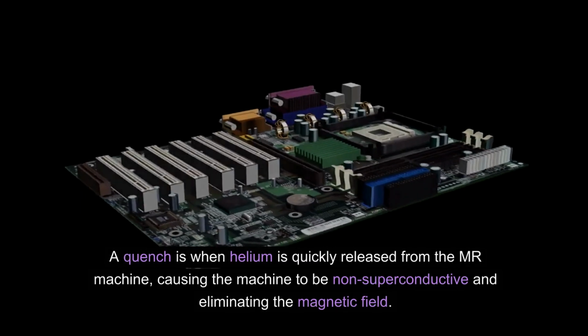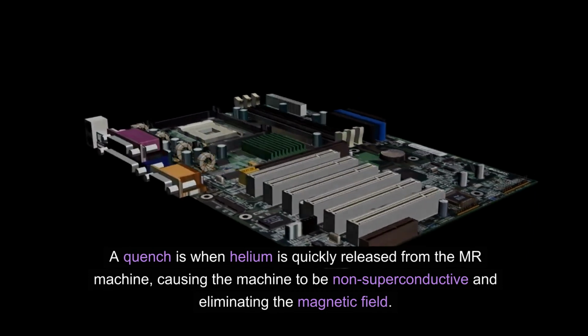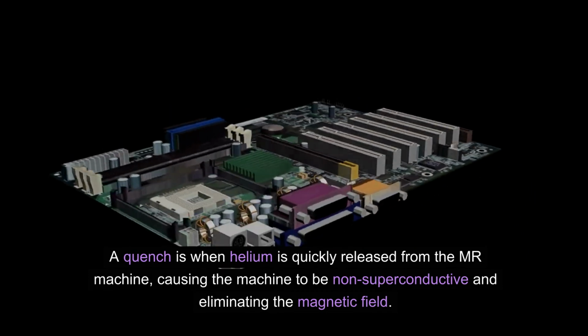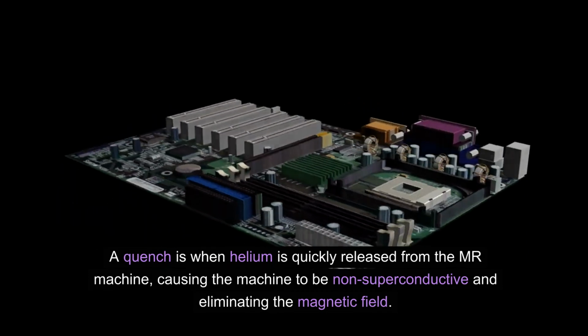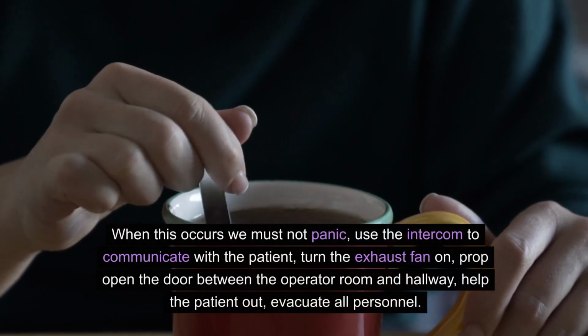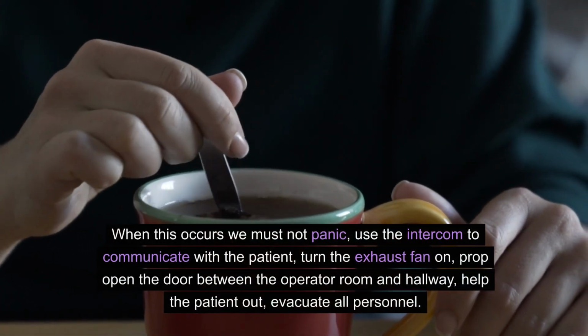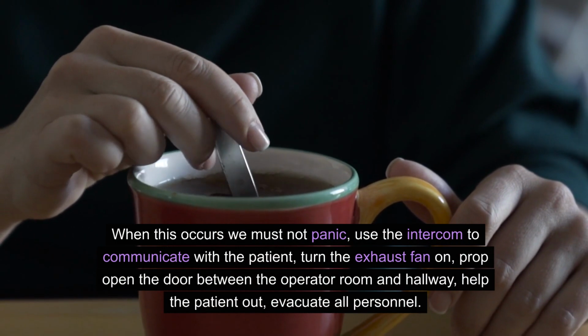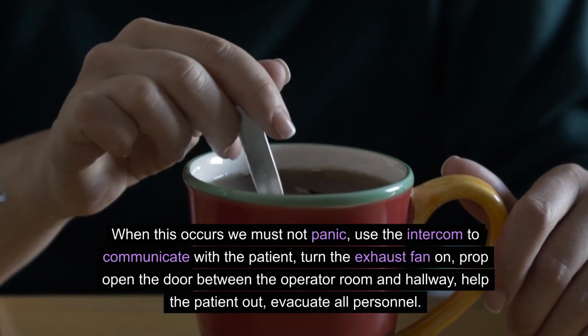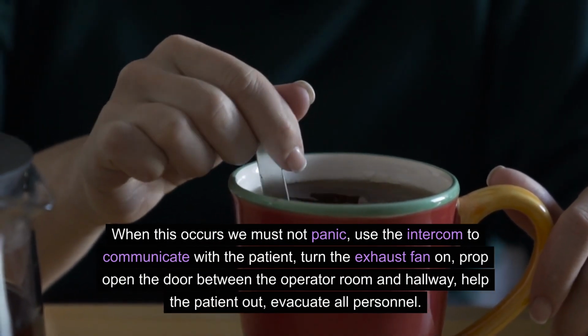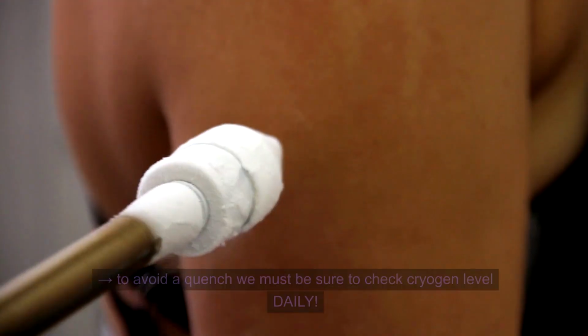A quench is when helium is quickly released from the MR machine, causing the machine to be non-superconductive and eliminating the magnetic field. When this occurs, we must not panic. Use the intercom to communicate with the patient. Turn the exhaust fan on. Prop open the door between the operator room and hallway. Help the patient out. Evacuate all personnel.